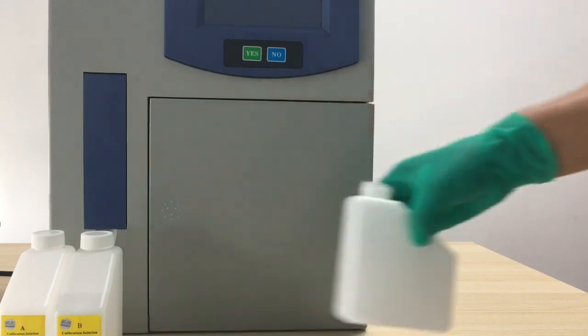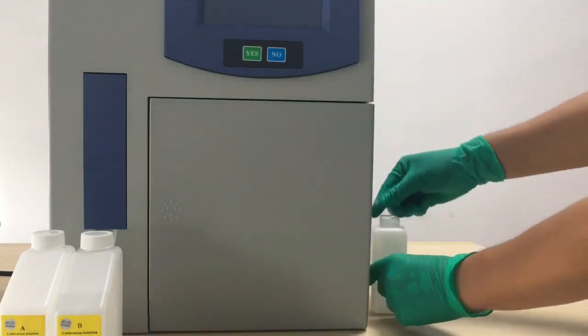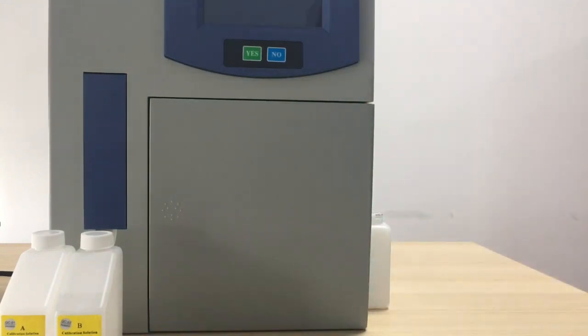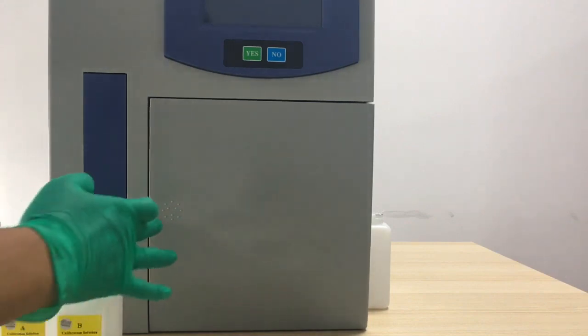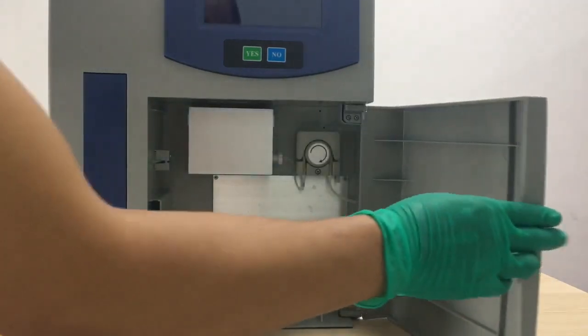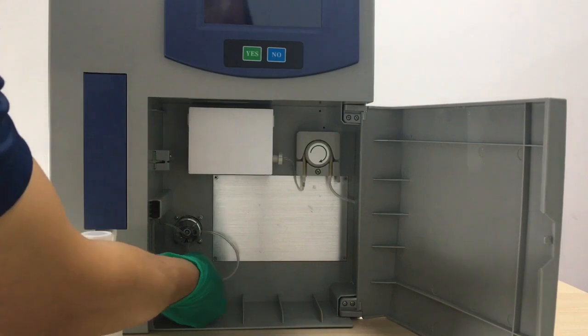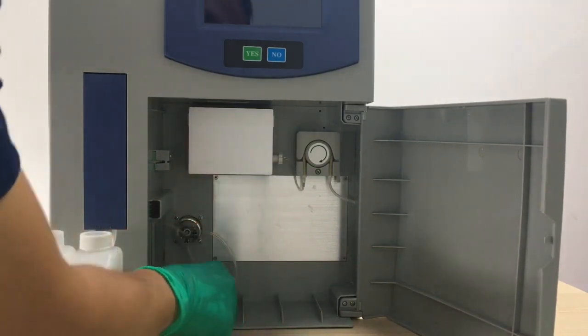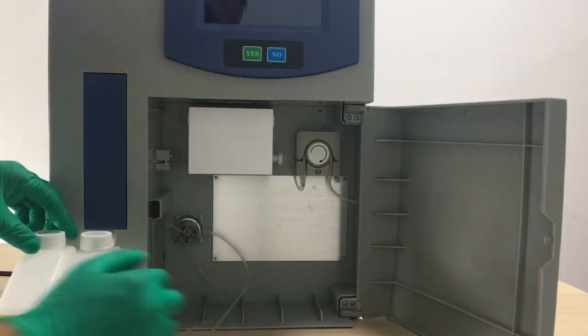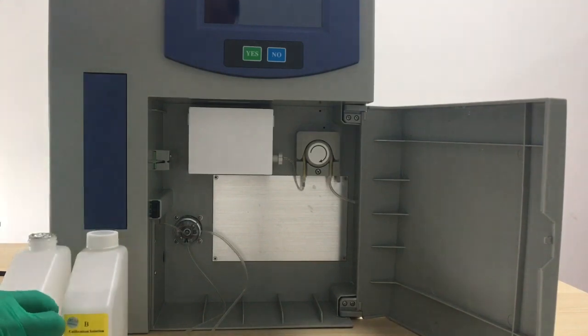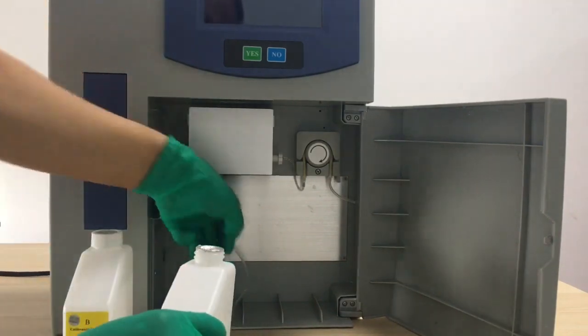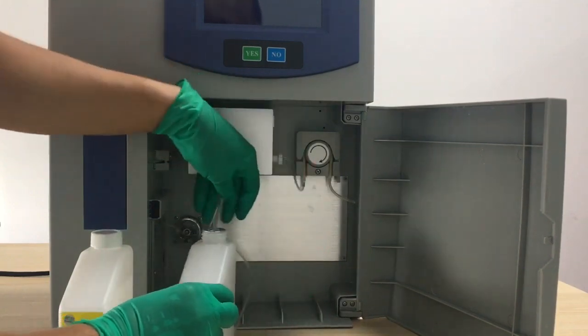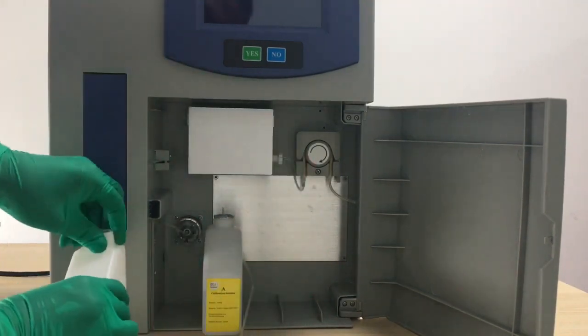Now we put the waste bottle outside of the machine and put the tube into it. Then we can open the door. We put the reagent, calibration A and B, in the right position. We need to pay attention: A is at the downside of the distribution valve, and B is at the right side.